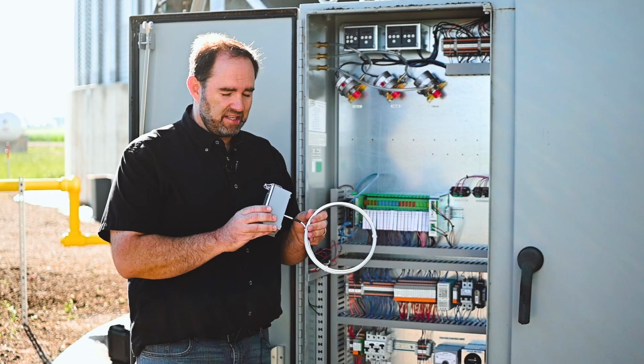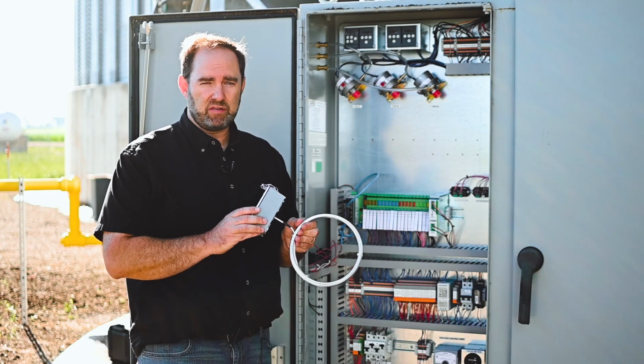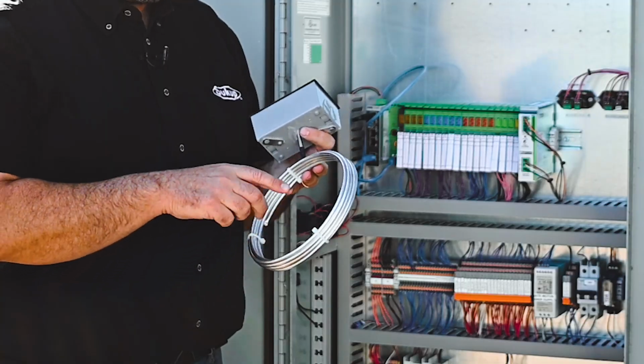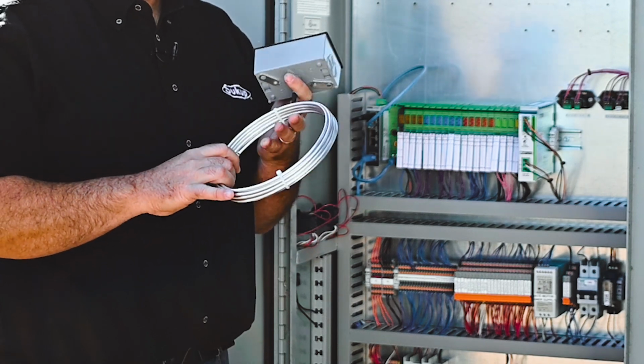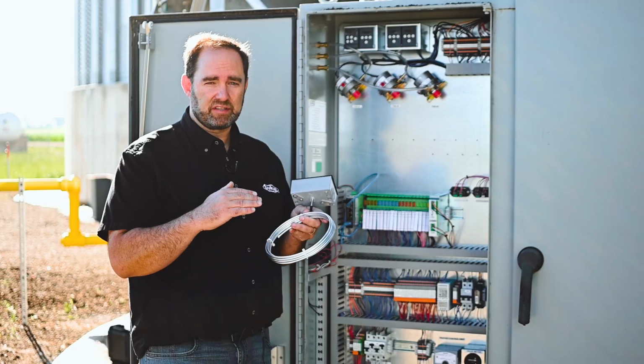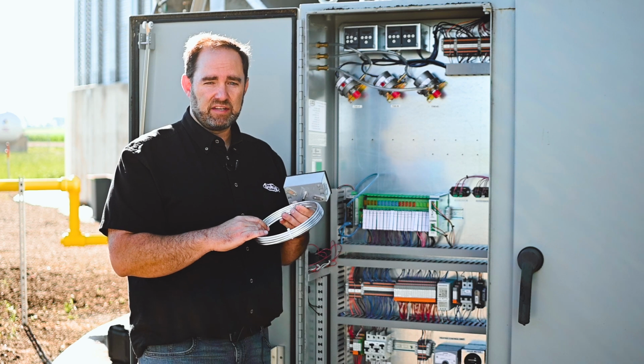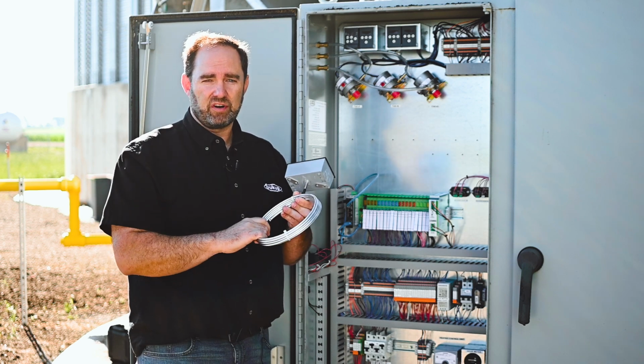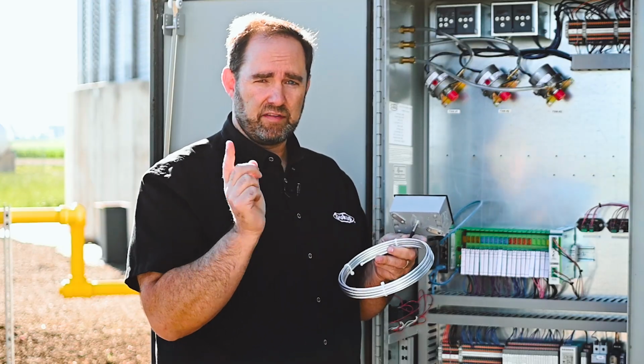Okay, so this is an RTD, and this is an averaging RTD that would be used in the plenum. So this is how they come. Obviously, it would be unrolled. This would be in the heater section, which on a tower dryer is going to be the second door up from the bottom. And as you walk in there, it's going to be about head or shoulder high, stretched out as far around the circle as we can.